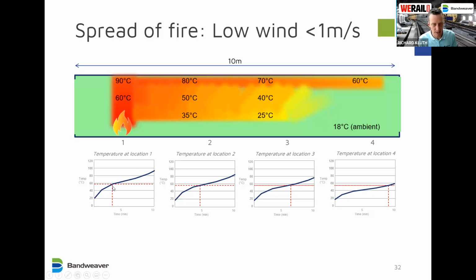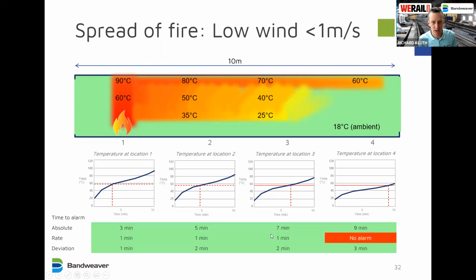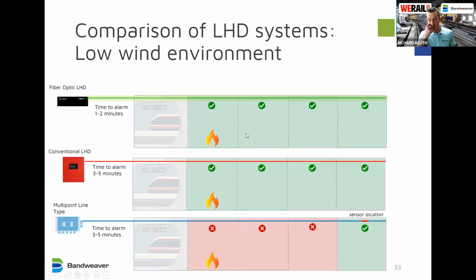You can see this red line is the absolute temperature alarm. And so this is when it's triggered. So you can see how many minutes it triggers in. But you can see in all cases, it triggers the absolute alarm a bit slower the further away you are from it. And if we look at this matrix here, the absolute rate deviation at each of these zones, we can see what the timing is at each one. I won't go into all the details at this point, but broadly speaking, you see pretty much everything triggers except for in zone 4, it's not quite fast enough to do the rate of rise, but otherwise you get full alarming at all zones. So what that means is the fiber optic linear heat detection, it triggers in all zones.